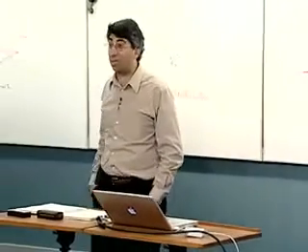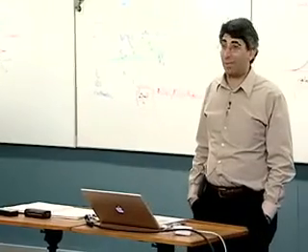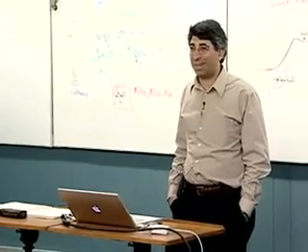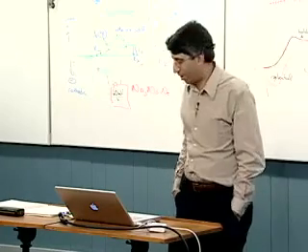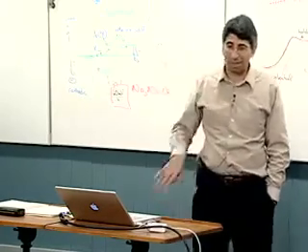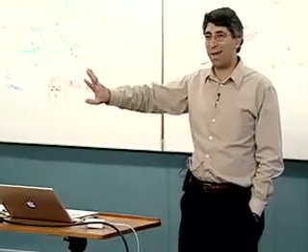Okay, so one has to make sure one has a potentiostat that can do what it's promised to do. You might want to look at a system that you're sure is reversible, like the ferrocene system, for example. When you have a brand new potentiostat, put it through its paces and see if, just because the knob says it goes at 100,000 volts per second, it really does. Okay. The second thing is, although the manufacturer is responsible for what happens inside the box, you're sort of responsible for what happens outside the box.